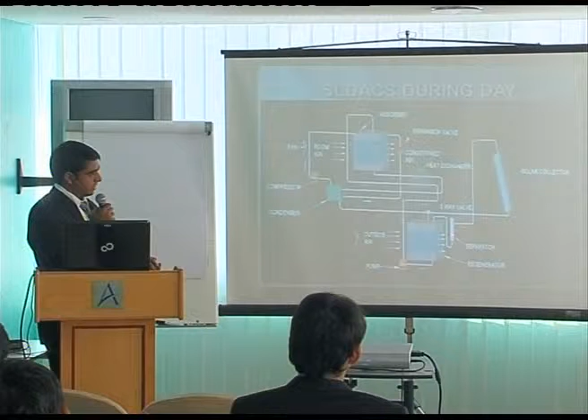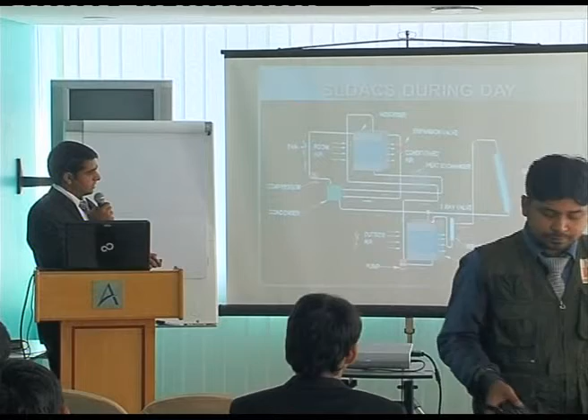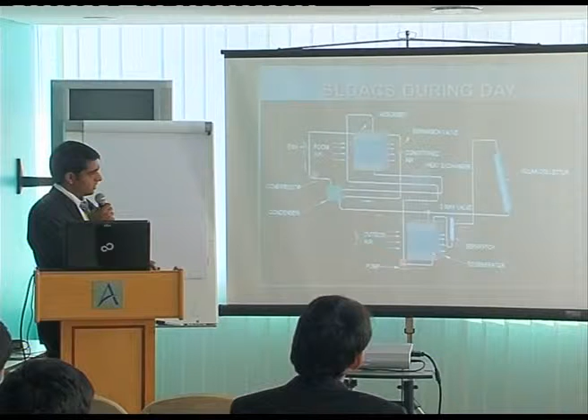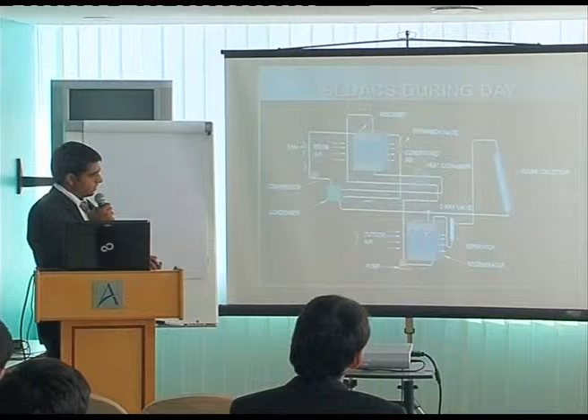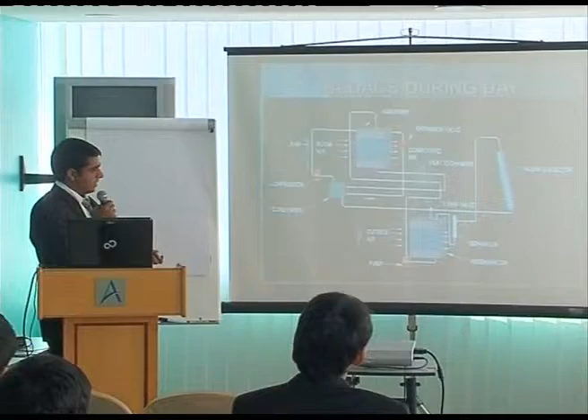This is the first stage of the regeneration part. Here the separation will take place and the vapor will be separated from the liquid. And the separated liquid desiccant, having the same temperature, will move to the second stage of regeneration. The second stage regenerator is similar to the absorber, consisting of the same honeycomb mesh, and the weak liquid desiccant is made to flow over this mesh, the same as we had done before. The outside air is blown with the help of a fan through this honeycomb mesh, and what happens here is the liquid desiccant will lose moisture to the outside air and the air will be rejected to the surrounding. This happens because of the pressure difference.